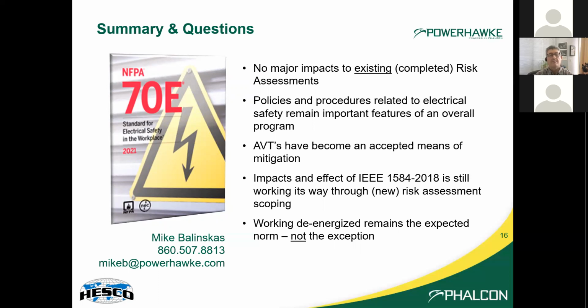And the second part, Chad, was what? Oh, gotchas. What are some things that are overlooked? When people first started doing arc flash risk assessments, one of the things they did was assume the utility at a maximum. You really can't do that. You really need to get the appropriate utility available short circuit current information, available fault current information, because the problem with arc flash is that it's not necessarily intuitive. You would think that higher voltage, higher current systems or devices would have worse risks, worse incident energies, and that is not always the case.